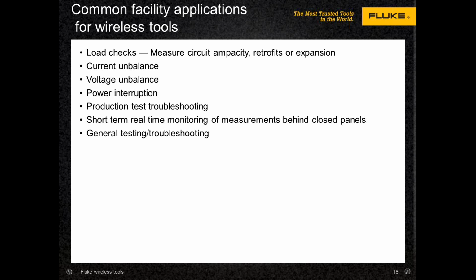So to do that, conventionally, you'd have to do one current measurement at a time over 3 phases. We're assuming that in some cases this is 3-phase, or it could be single-phase for that matter. With 1 meter, you're going to get 1 measurement at a time, and if you check that during the day, you're going to have to guess at how that ampacity shifted or changed during the day. With the wireless stuff nowadays, and especially with the logging capability, you can look at that load variation over the course of a day, a shift, a couple days, or whatever, to see how that load varies, and so you can get a good reading on the average current load at any given time. And so then you know what your maximum ampacity is.